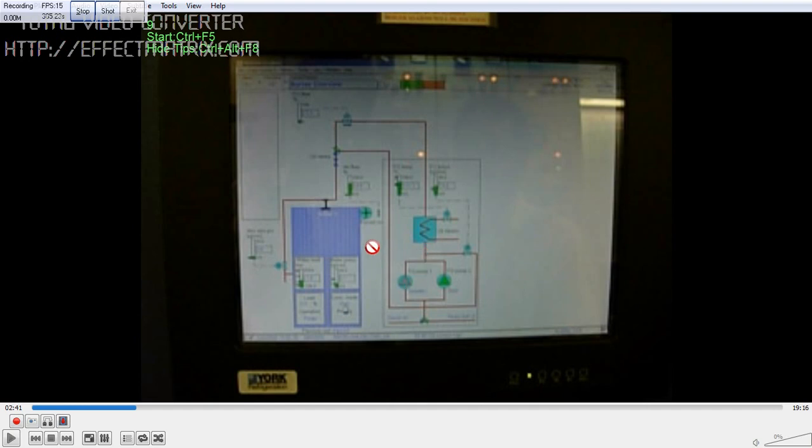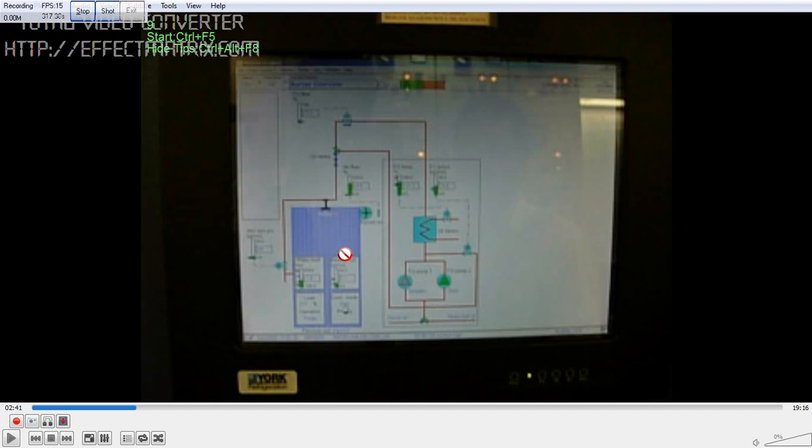Again before starting, when the boiler pressure drops to say 6 or 6.2, it will start. Then it will stop at 8.4 bar pressure. So this is the sequence, all the safeties are there.